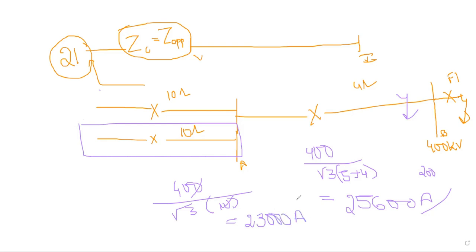So what I am saying to this breaker, to the line when I am grading, if the fault lies between this period, then it has to be operated. But will you confirm whether the fault will be in this range? It's practically impossible. So that is also one more disadvantage of using this overcurrent relay. So to avoid all these scenarios, we will implement the distance protection. We will be talking about the distance protection.